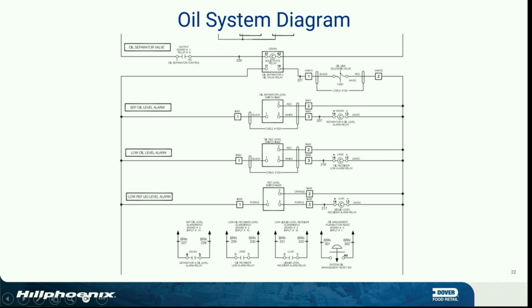Yeah. Dude, click. So, all right, our oil separator level indicator turns on and energizes our OSLRA relay. That gives us an input, which tells the controller to start cycling our solenoid. So next in line, our output board will tell our solid state relay. The reason we use the solid state relay is we're going from whatever the closure voltage is, anywhere from 24 to 220, to a dry contact, right? That'll go through our output board to our solid state relay. Our solid state relay is capable of a lot of pulses, so we put that in there. It's a little bit more rugged than just the output board, even though it's like a half amp. It'll just withstand it. And then that solid state relay pulses our solenoid.